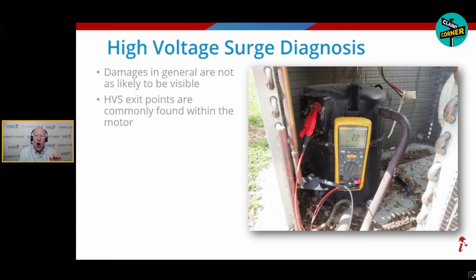And let me tell you about a few other things that are either portrayed as or misidentified as lightning or surge. Okay. And these are things that are showing up all the time in claims, and you're going to want to be on the lookout for these types of things. The first one is resistive heating. If you have not heard that term before, basically what it means is when electricity is flowing through the wires, if you resist it, meaning slowing it down, it gets hot or hotter, right? It can be red hot, literally red hot. So when something's going on in the system and that's resisting the flow of electricity, it heats up. When it heats up, it causes damage. So resistive heating happens over a period of time, not sudden and accidental. Those all should be terms that are resonating with you as far as whether you're covering this or not, right?